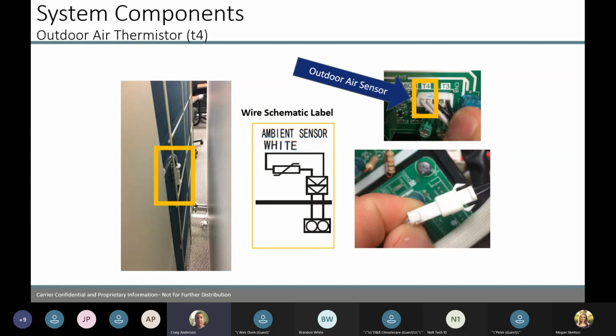So be mindful of how they've located it. If it's too close to a wall, we're not getting proper airflow through there. It's heating up in there. Clearances mean a lot with these units because we're dealing with so many parameters with air sensors and temperature sensors.